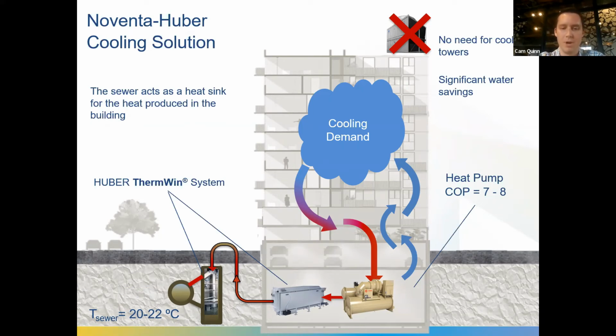So what happens with what we call the Noventa Huber cooling solution if we're using wastewater energy transfer? What changes? A couple of slides further in the presentation, I'll go more into the details of these two pieces of equipment and how they work. But at a high level, we're still using the same chiller in the basement here, but instead of connecting it to a cooling tower, we're connecting it to a heat exchanger. And this heat exchanger exchanges energy with sewage.